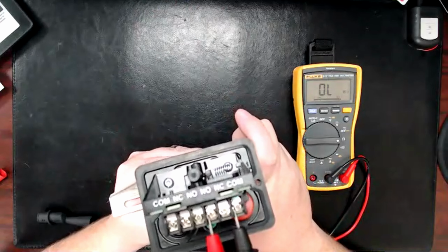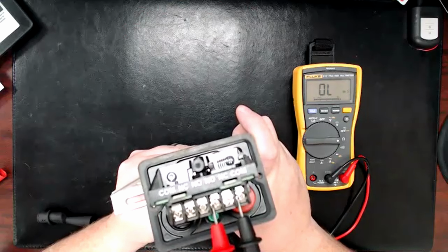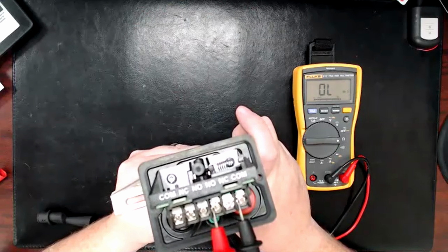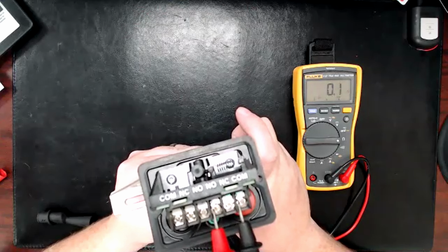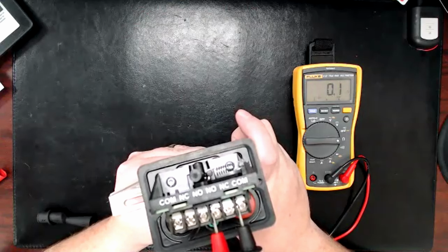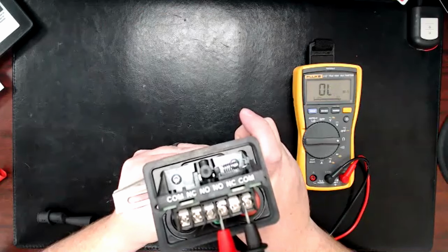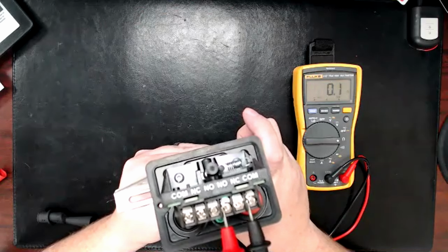If I were then to get the resistor to sit between those, this is when we would read the resistor. And then as you turn the valve, it would slowly push on it and you'd hear that click and it shorts. When it shorts, that's when we get our supervisory or alarm signals, is when our meter reads a short like it is right now. And then you let it back up a little bit, and then we go back to that open line. And if I let it back up more, it goes back to that shorted condition.